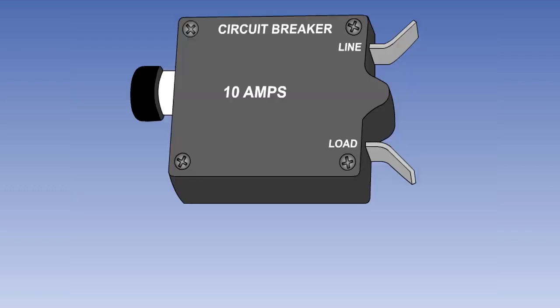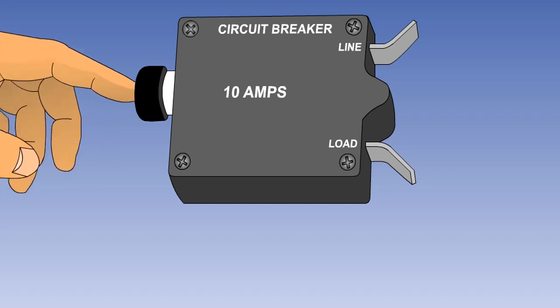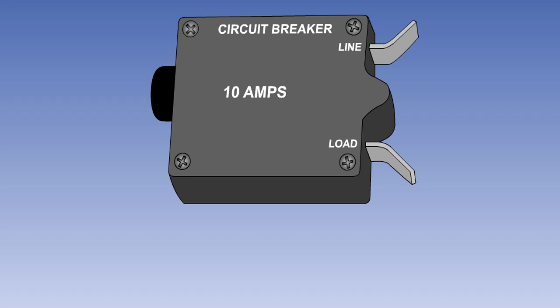Unlike the fuse, a circuit breaker may be reset after it is tripped. Like the fuse, this should be done once only. If the circuit breaker trips again, the fault must be investigated before a further reset is attempted.